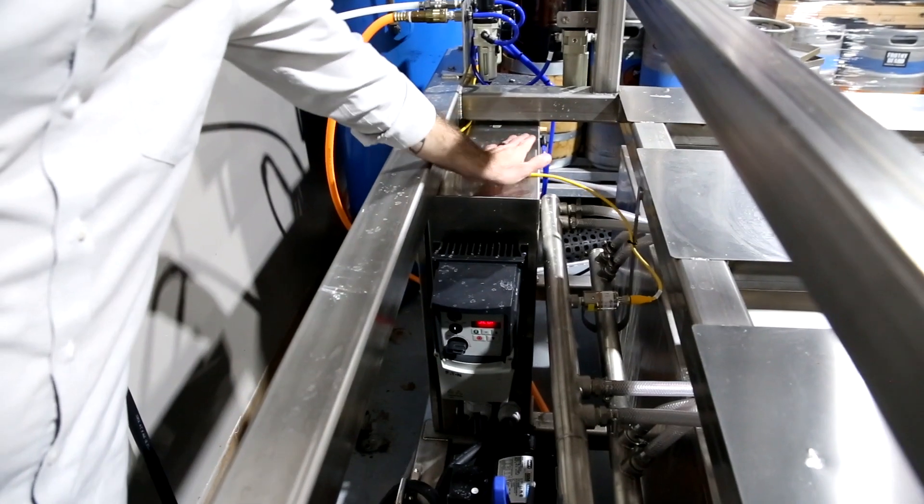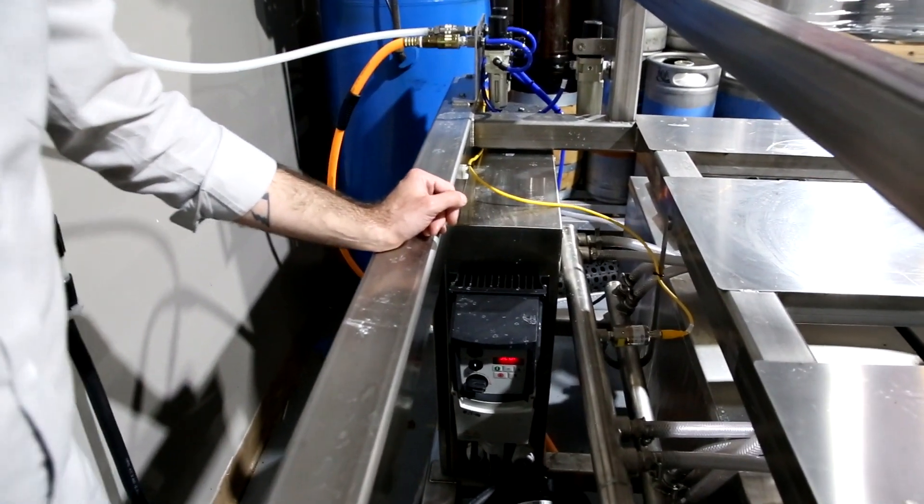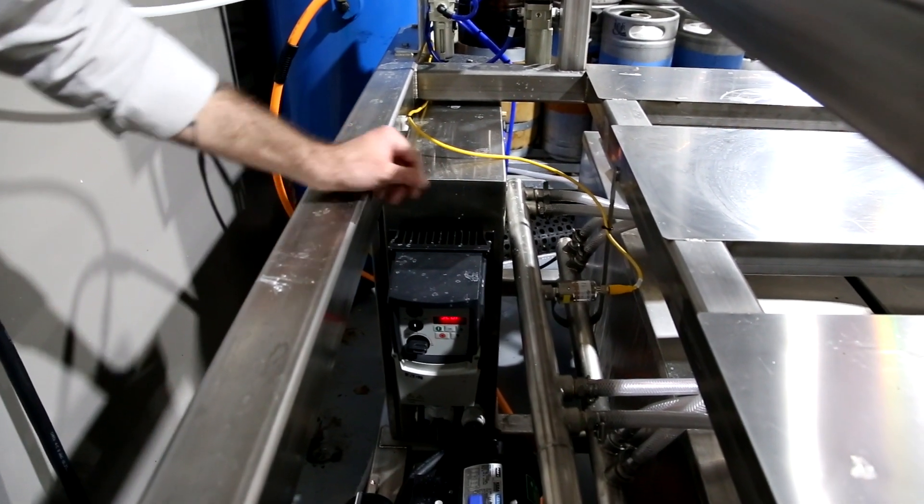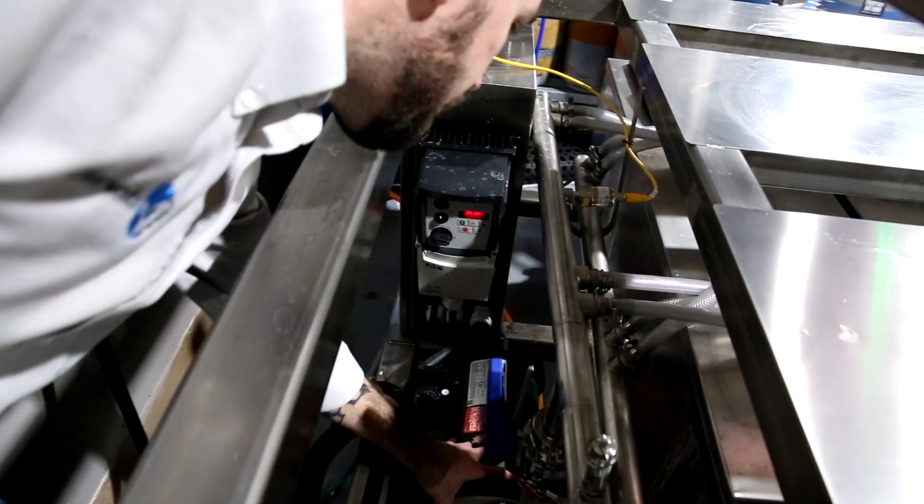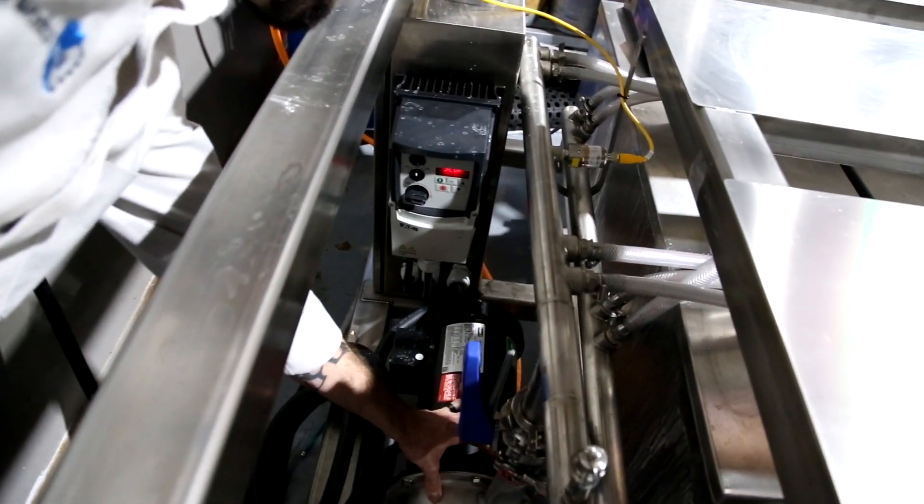On the back side we have our industrial control panel housing the PLC controller. For this machine we use an industry standard S7-1200 Siemens product. We've got a wash down rated VFD and drive, running a wash down rated AMT pump. Stainless steel shaft and impeller, 2 horsepower.